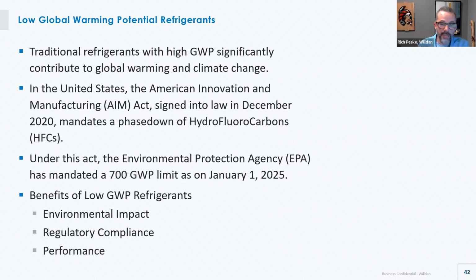These lower GWP refrigerants have a much lower impact on global warming compared to their higher GWP counterparts. And if I didn't say this earlier, you're thinking, wait a minute, it's a closed system, right? So what does it matter what's inside it? They do leak.